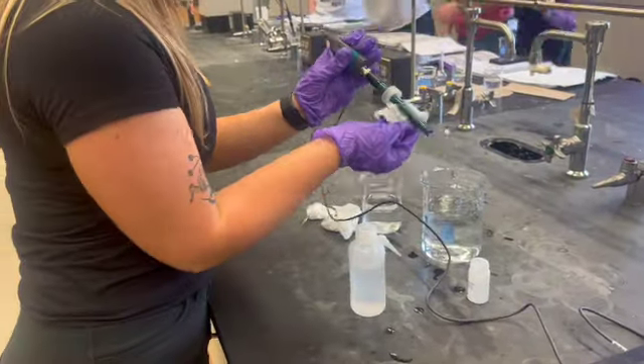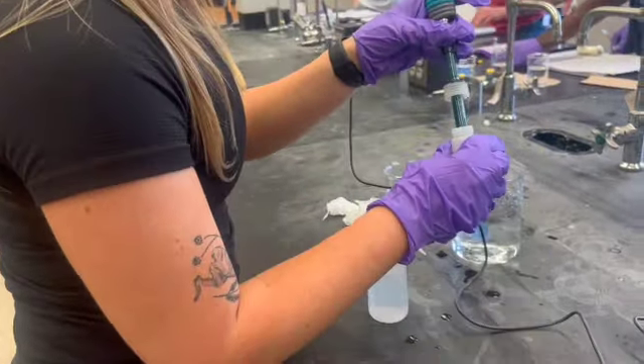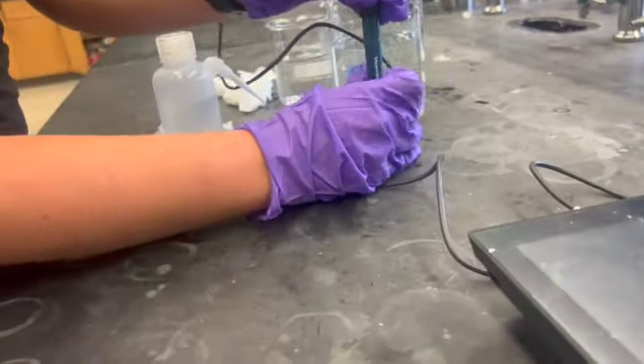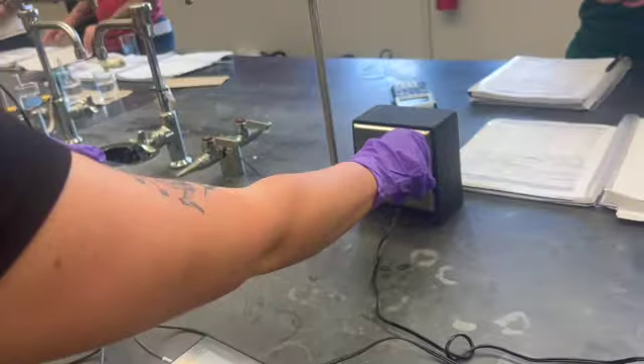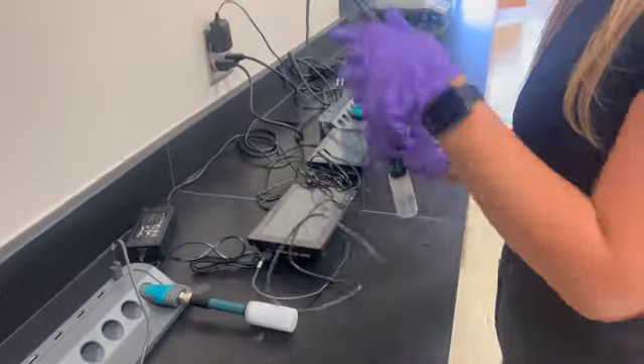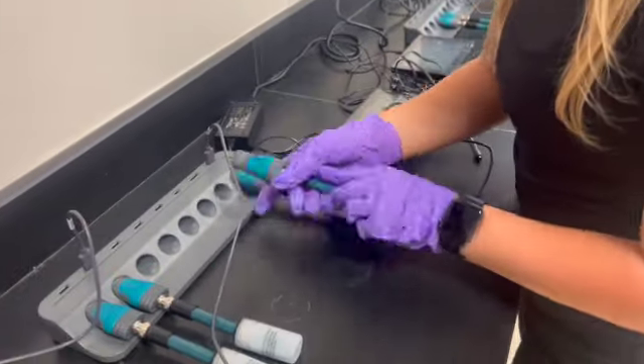When cleaning the pH probe, it is important to rinse off and dry the probe. Once the probe is clean, place it into the storage solution that came with the probe. Unplug the monitor from the wall and bring the probe and monitor back to the charging station. Unplug the probe itself from the monitor and slide it back into a spot on the charging dock. To finish the cleaning process, plug the monitor into the wall.